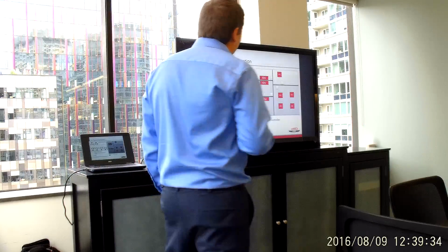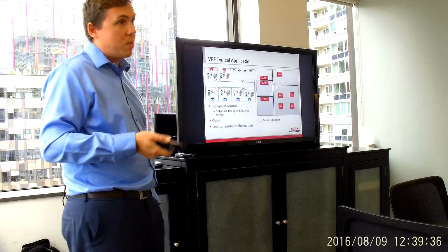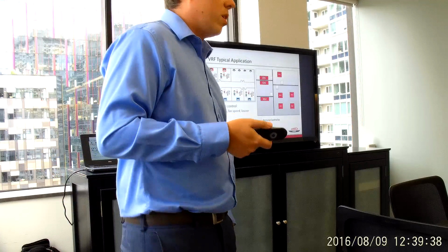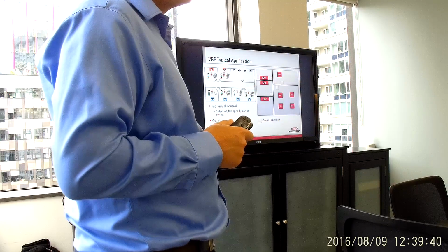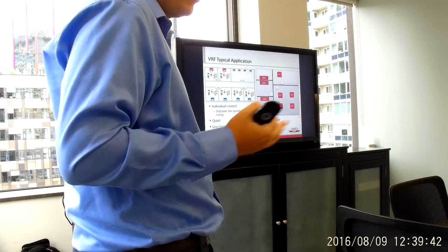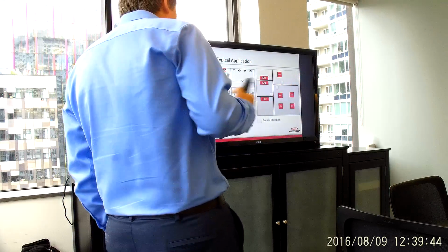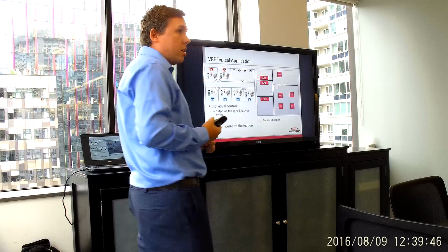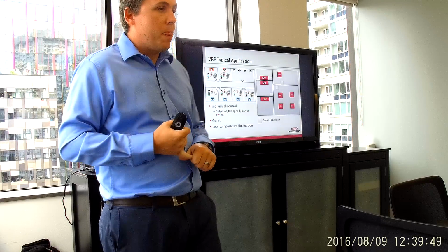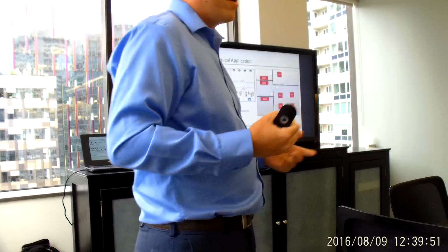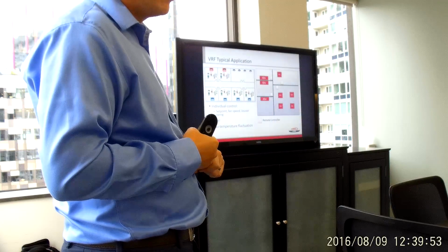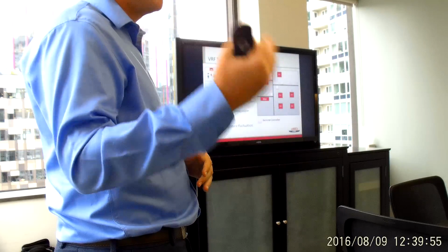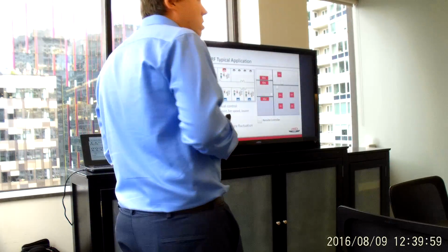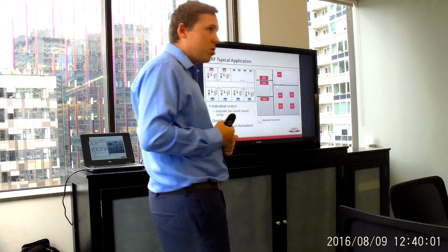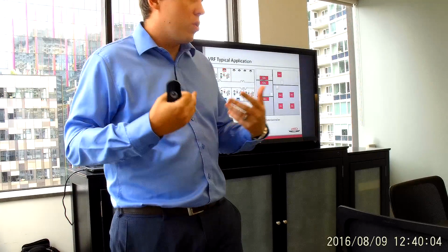So as opposed to spending $3,500 per ton on a makeup air unit, you spend $1,700, $1,800 per ton, maybe even a lot less, depending on what you need, for a rooftop package unit. And you get cooling as a standard. The reason why it's so high is because it has to be an Energence with Humiditrol and an economizer and so on and so on. So all the extras get added on. So that's something to consider. Low cost solution for a system like this.